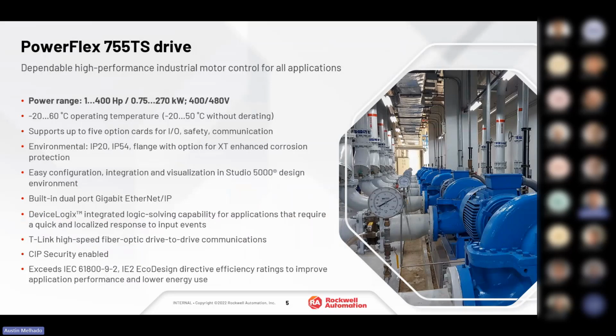If you did a derate, meaning you had a 10 horsepower motor and upsized the VFD so it's not running as hard, we can actually get up to 60 degrees Celsius, which is pretty good, especially for HVAC applications on top of a rooftop or a high temperature room.